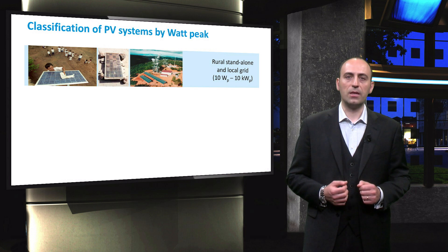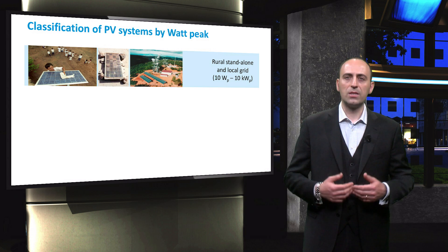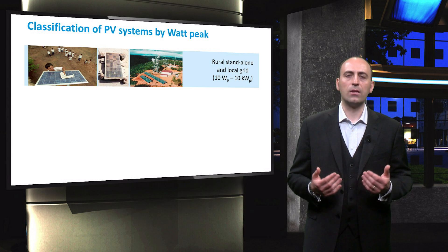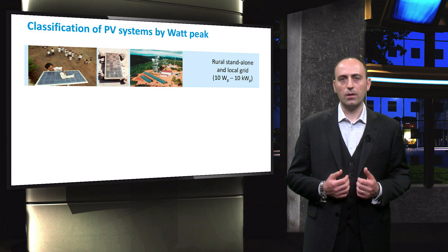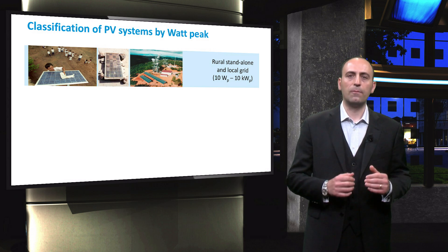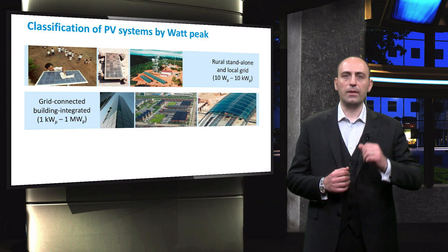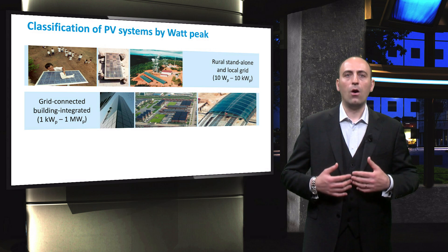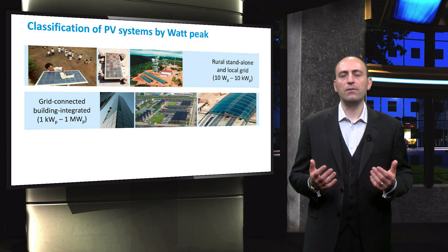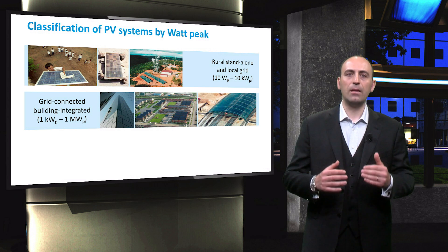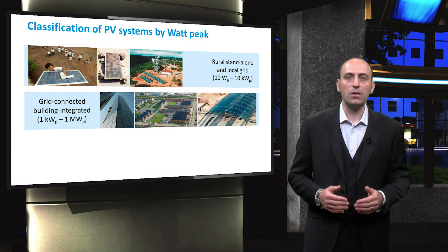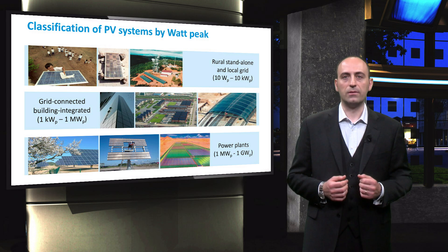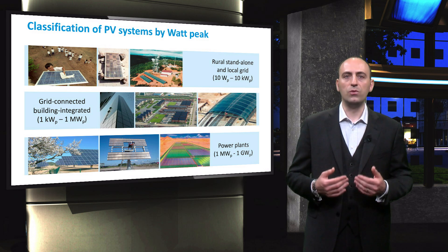Another way to classify PV systems is by installed peak power. In the first category, we have rural or standalone systems with eventually a local grid. In this case, the rated power is quite low, between 10 watt-peak and 10 kilowatt-peak. Going up in power, there are grid-connected building-integrated systems, which can be found for example on the façade of a skyscraper, on the rooftop of residential buildings, and on train stations. This topology is easily scalable from very small systems in the range of 1 kilowatt-peak to megawatt-peak scale installations. Finally, we have power plants with a peak power of several megawatts, which are connected to the electricity grid via three-phase inverters.